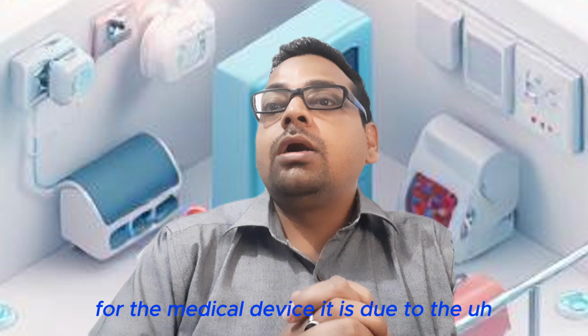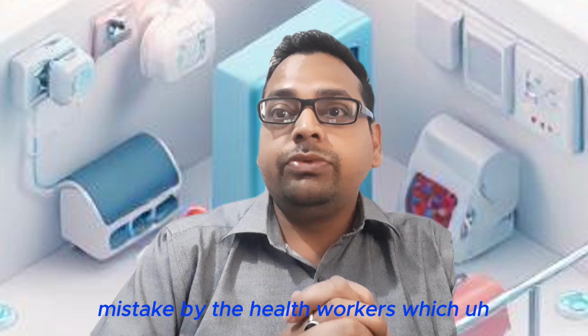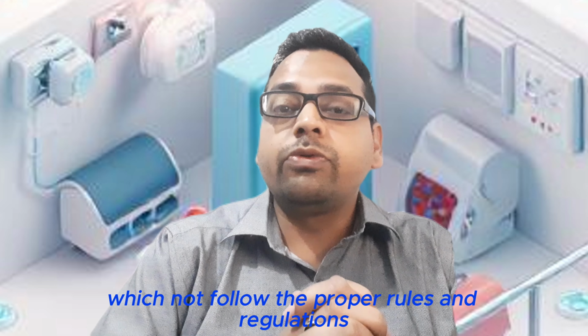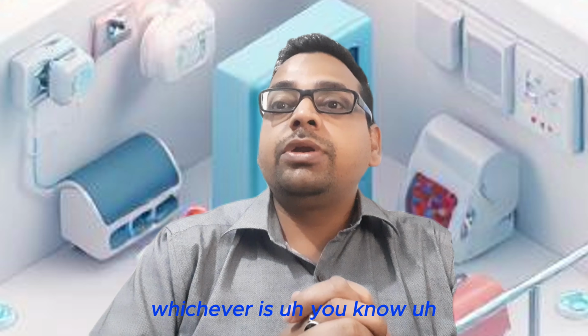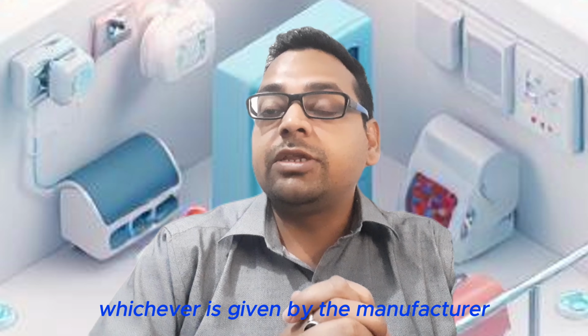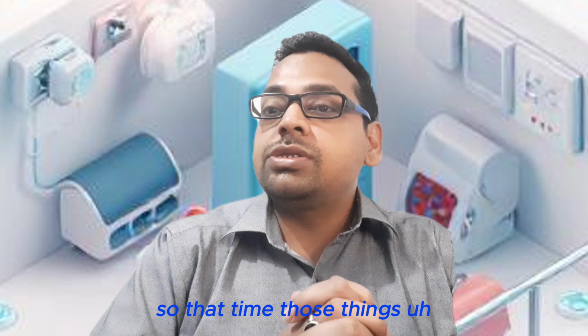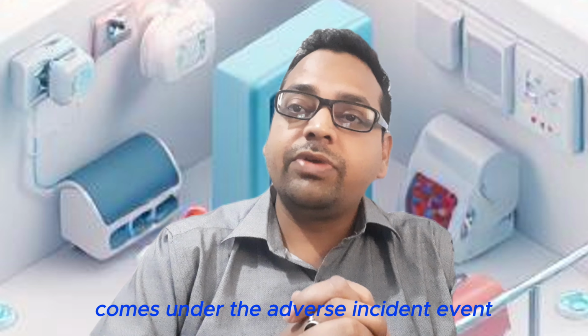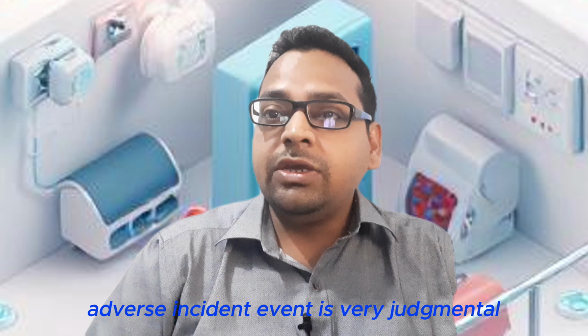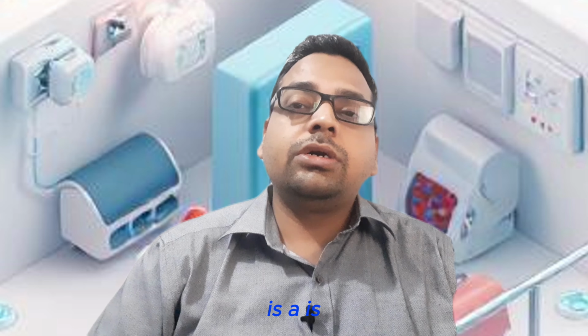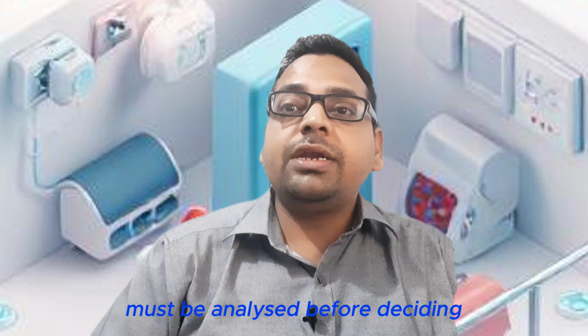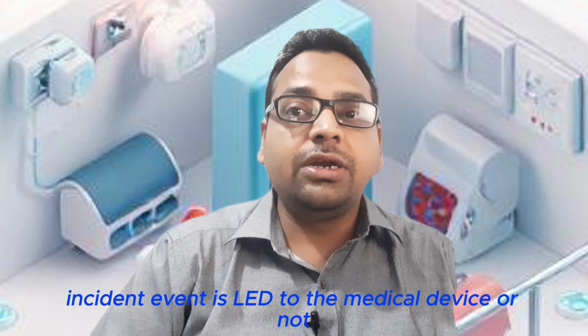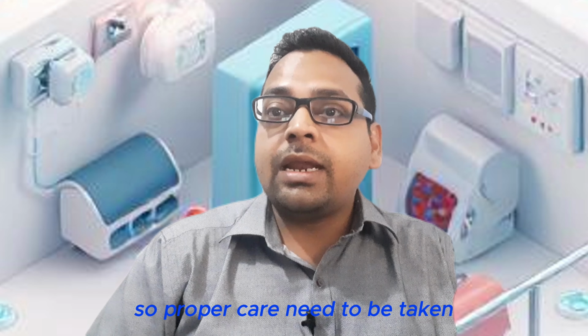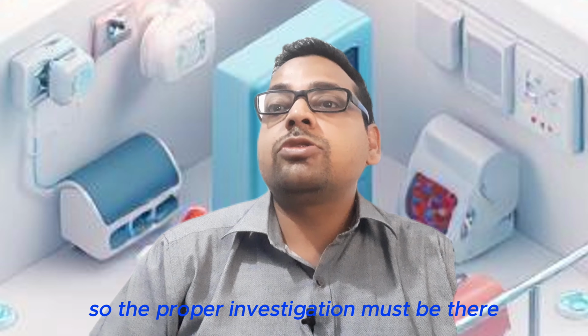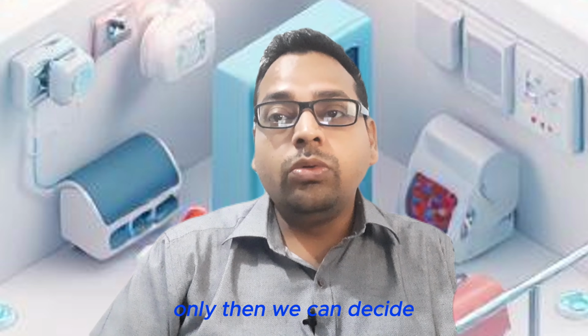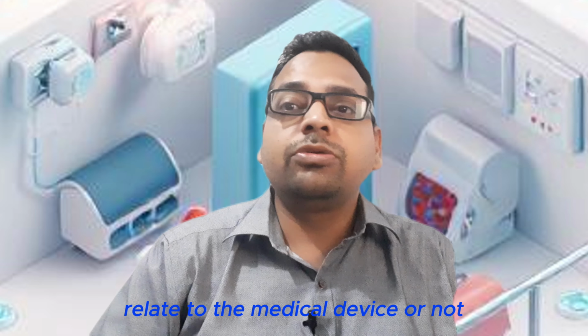It is due to a mistake by the health workers, who did not follow the proper rules, regulations and protocol given by the manufacturer. So that time, those things will not come under the adverse incident event. Always remember, an adverse incident event is very judgmental and must be analyzed before deciding whether it is related to the medical device or not. Proper care needs to be taken. Even if a complaint arises, proper investigation must be done. Only then can we decide whether the adverse incident event is related to the medical device.